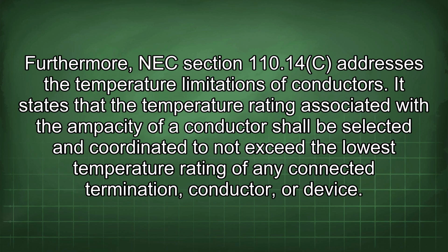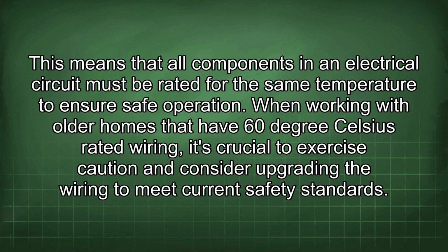Furthermore, NEC Section 110.14(C) addresses the temperature limitations of conductors. It states that the temperature rating associated with the ampacity of a conductor shall be selected and coordinated to not exceed the lowest temperature rating of any connected termination, conductor, or device. This means that all components in an electrical circuit must be rated for the same temperature to ensure safe operation.